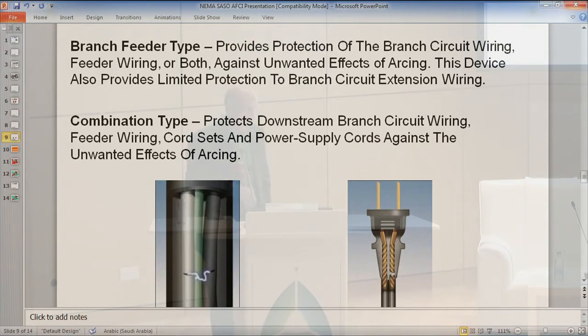I think in terms of general wiring practice, when you introduce these, I've seen wiring installations become much better as a result of these devices. Because if you don't do it right, or if you do it sloppy, the circuit breaker tells the story. And so we have a lot of situations where we say, your breaker is tripping, it's bad. And then you go in and you find out that you've avoided a fire. And it really does help with improving the installations.